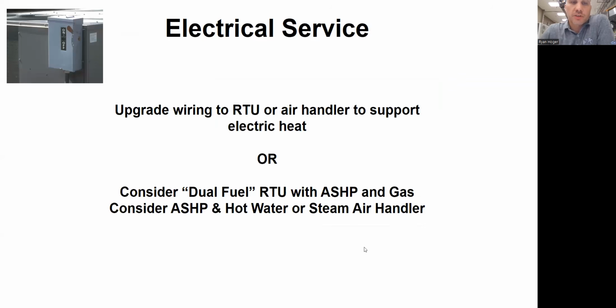All right, so electrical service might need to be upgraded for rooftops or air handlers to support electric heat. If it's an air handler, meaning it's a split system, an indoor and outdoor component, the outdoor unit probably doesn't need anything different from a wiring standpoint. It's the indoor unit where the electric heater would be located that would probably need something different. If it's all electric, probably fine. If it's a fossil fuel conversion or a hydronic or steam conversion, then you would probably have to add electrical wiring to the indoor unit.